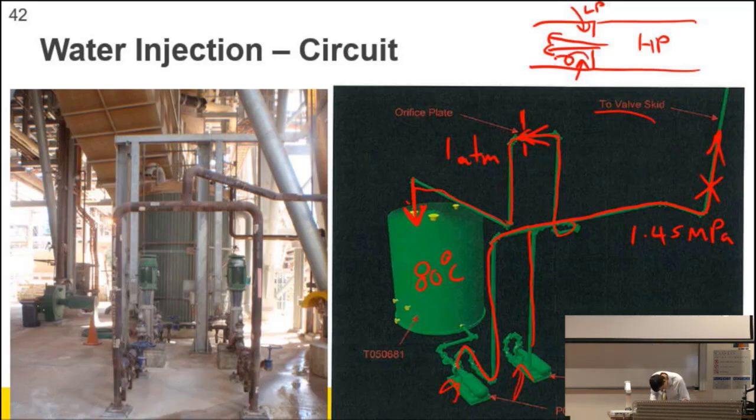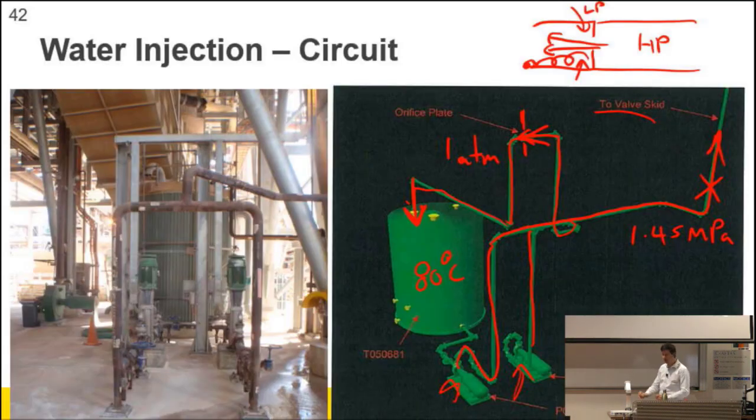And then that sheds downstream and then recondenses. And as it recondenses with a lot of pressure, it actually eats the metal away. So we were getting the pipe downstream wearing through the steel. Okay?